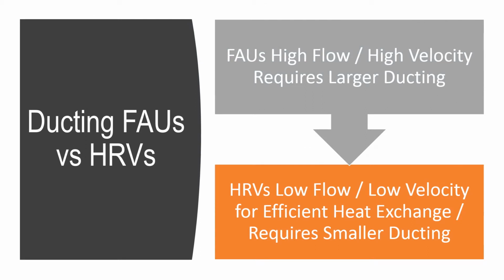High velocity, high volume air provided by forced air units requires large ducting. Low velocity, low volume air provided by heat recovery ventilators requires smaller ducting to be effective. Mixing these systems is a typical practice in commercial projects, but it has a diluted effect. It is clearly better than no ventilation, but is certainly not an optimal way to deliver fresh air.